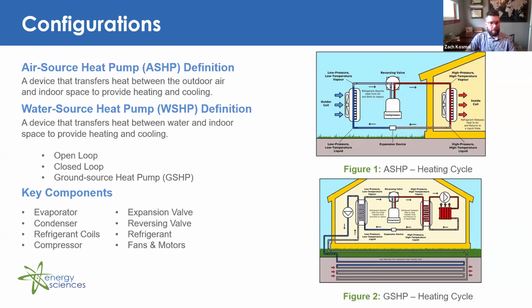Another type would be a water source heat pump, in which a device transfers heat between water and an indoor space to provide heating and cooling. So with water source heat pumps, they can be utilized in several applications. You can use pond or lake water. You can also use groundwater or well water for that heat transfer mechanism, in which the heat exchange occurs with the water instead of the ground for a ground source heat pump. And for cold climate applications, the piping is typically placed at a minimum of 8 feet under the surface of the water just to prevent freezing in that system.